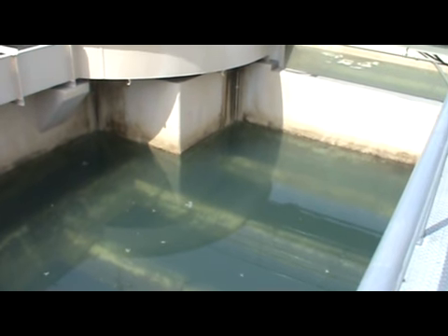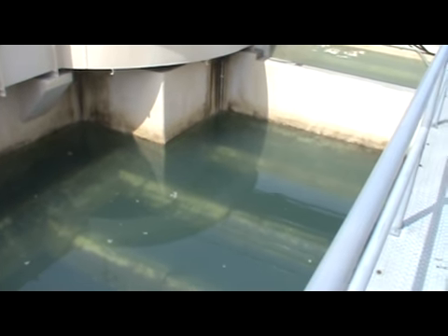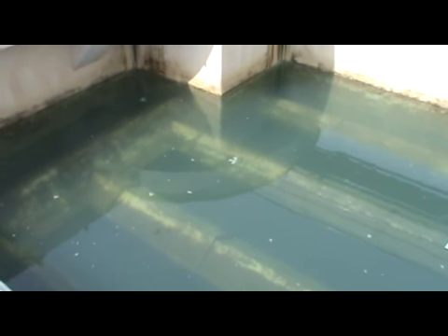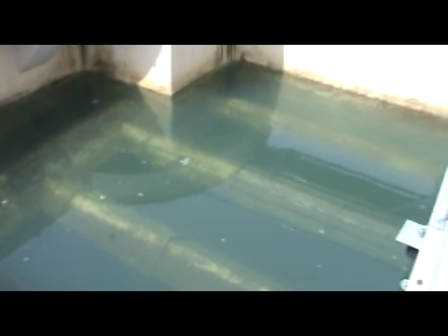As that filter bed material expands, remember I said the filter was drained down, so these troughs you see are actually right above the skim of the water level. And as you expand that media, everything that's captured in it, all those particles and junk and floc and turbidity, expands with it and floats to the surface and gets captured in that trough and carried to the washwater collection tanks, along with the water that was first sent when it drains down.